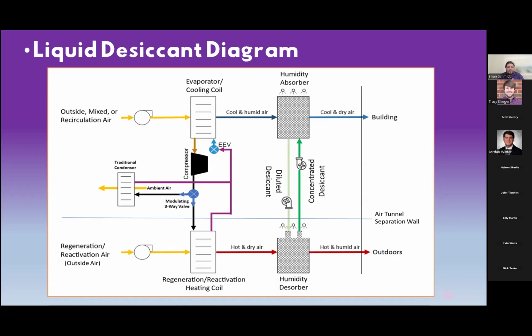It will not turn off the overall unit itself. So you're still going to be providing some dehumidification through the DX side. But again, the liquid desiccant system would be turned off. Alarms would be going off. Everyone that wants an alarm would be getting an alarm. Again, because there's catastrophic failure or there's a leak detected in the system itself.